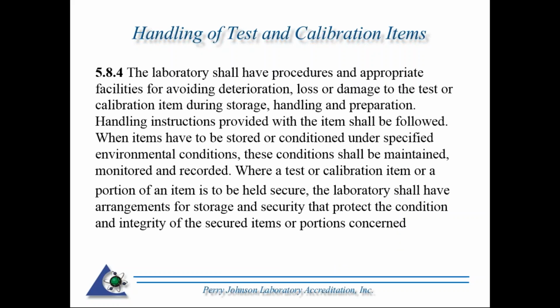Okay, clause number 4, 584, has to do with your facility. The laboratory shall have procedures and appropriate facilities for avoiding deterioration, loss, or damage to the test or calibration items during storage, handling, and preparation. Handling instructions provided with the items shall be followed. When items have to be stored or conditioned under specified environmental conditions, these conditions shall be maintained, monitored, and recorded. Where a test or calibration item or a portion of an item is to be held secure, the laboratory shall have arrangements for storage and security that protect the condition and integrity of the secure items or portions concerned.